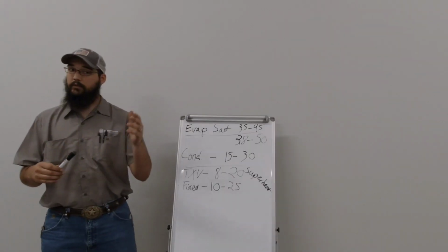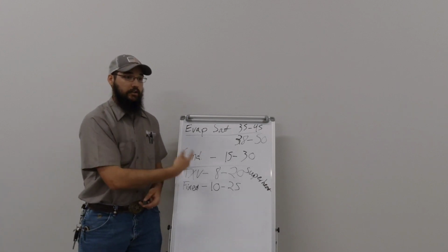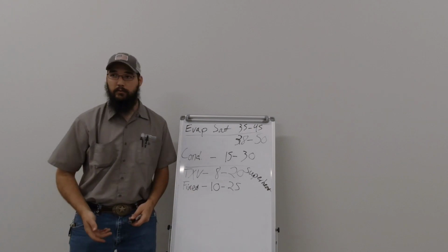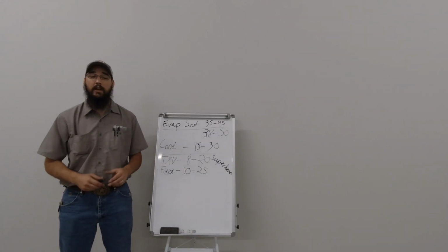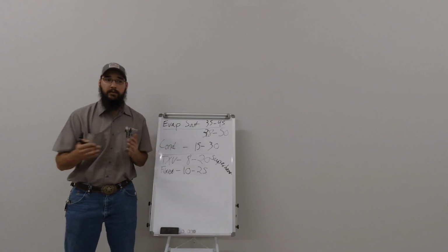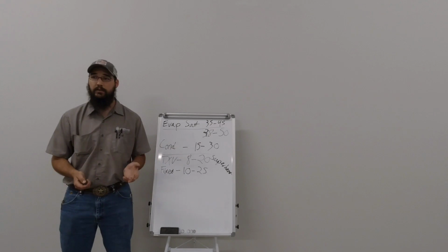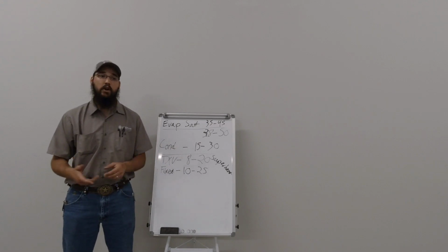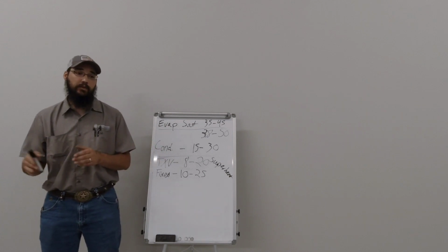This is where it starts to get even further into complication. It's already complicated just getting this far. We haven't even begun to talk about subcool. Now you start factoring multiple compressors in the same circuit. You have to think, okay, if I'm able to load more than just this one compressor, what does that mean for the rest of the system? That means I've got enough load on the system to support that. So the system is going to respond to that.